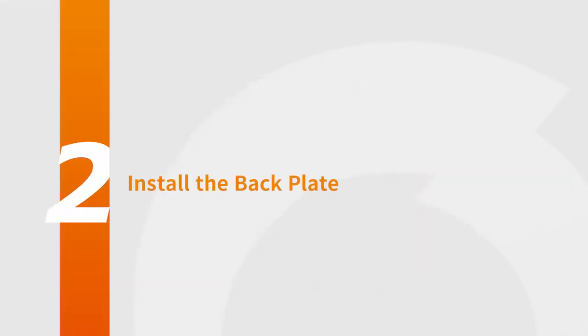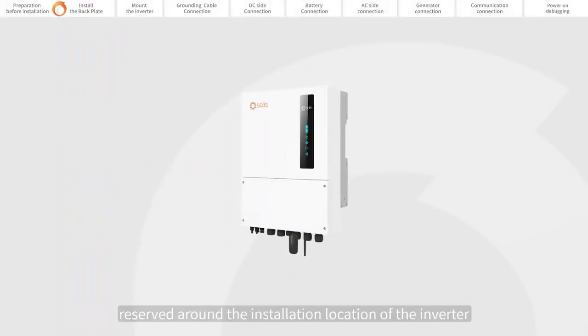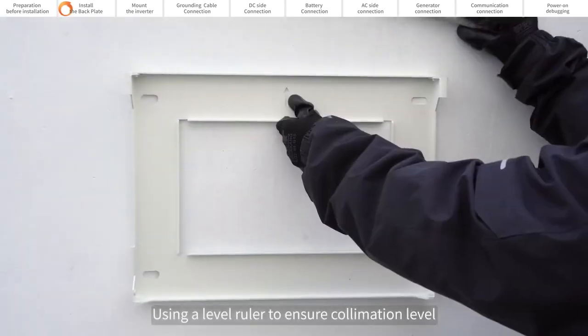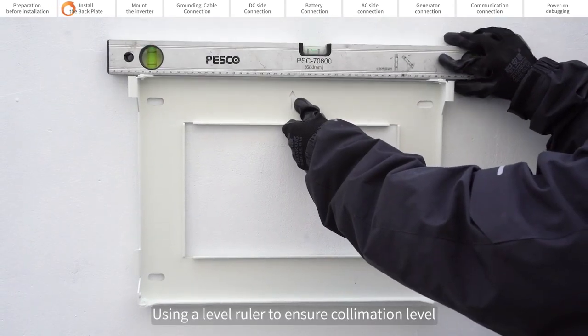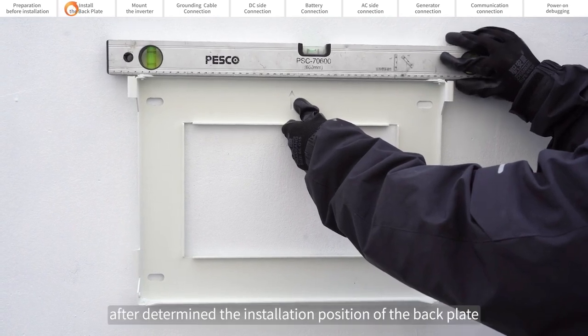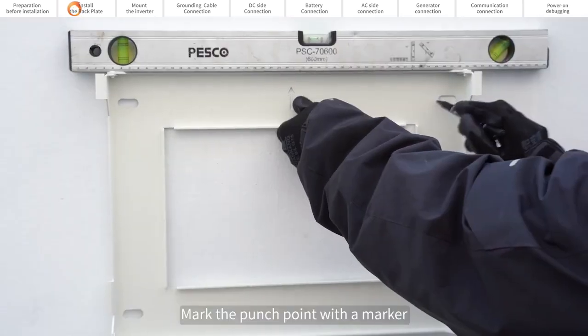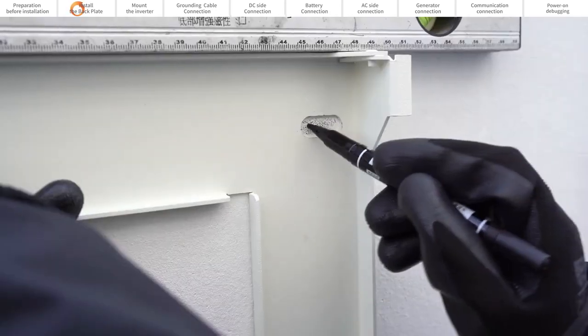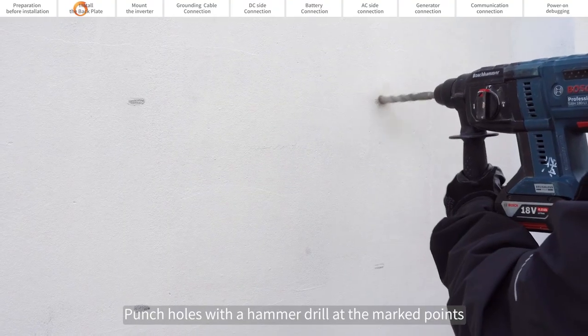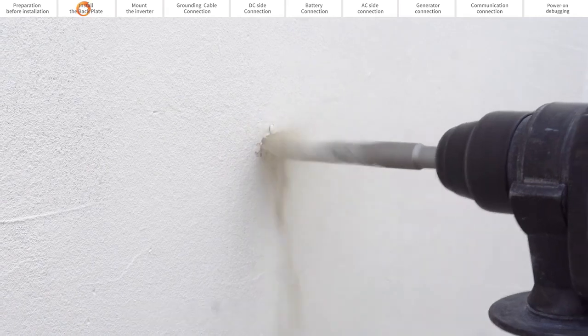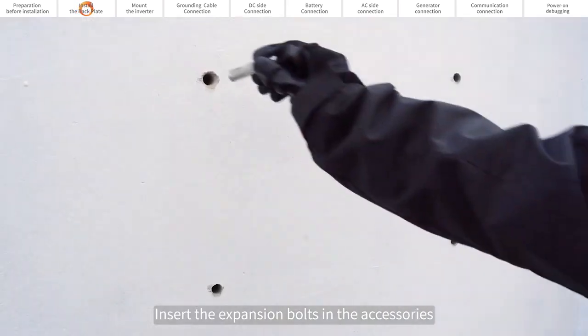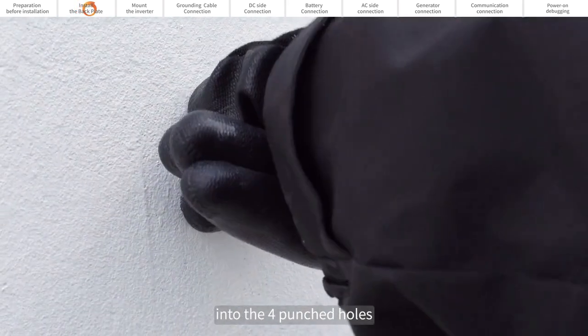Install the back plate. Appropriate space should be reserved around the installation location of the inverter. Use a level ruler to ensure the back plate is level after determining its installation position. Mark the punch points with a marker. Punch holes with a hammer drill at the marked points. Insert the expansion bolts and the accessories into the 4 punched holes.